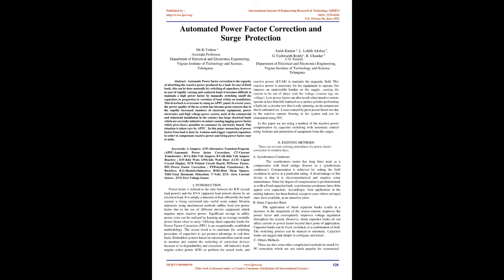Abstract: Automatic power factor correction is the capacity of absorbing the reactive power produced by a load. Reactive power, kVAR, is necessary for the equipment to operate and to maintain the magnetic field, but it imposes an undesirable burden on the supply, causing the current to be out of phase with the voltage. Current lags the voltage. In case of fixed loads, this can be done manually by switching capacitors; however, in case of rapidly varying and scattered loads it becomes difficult to maintain a high power factor by manually switching the capacitors on and off in proportion to the variation of load within an installation. This drawback is overcome by using an APFC panel.